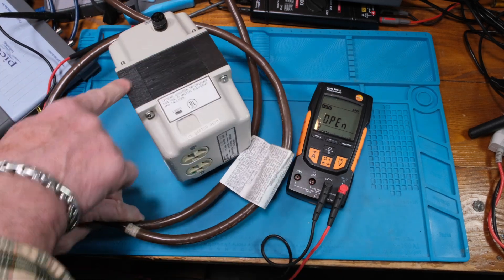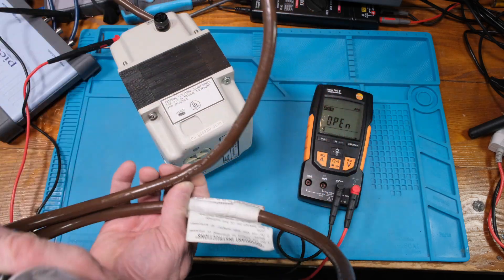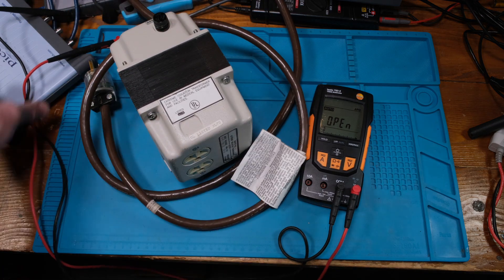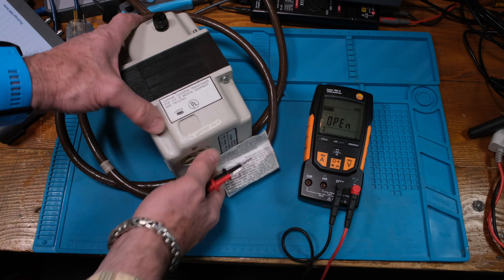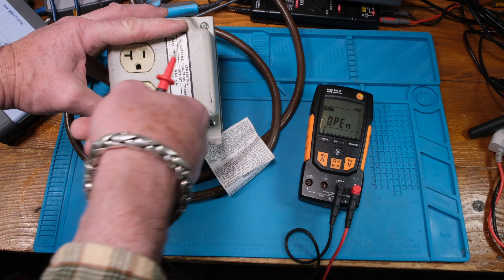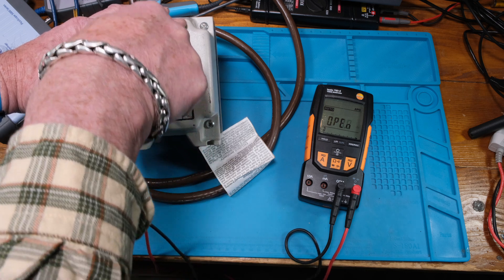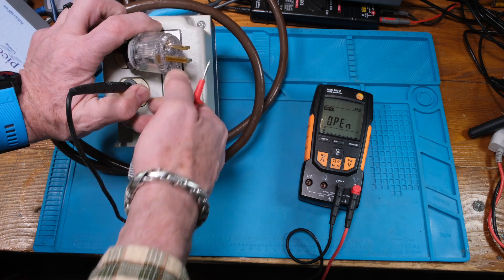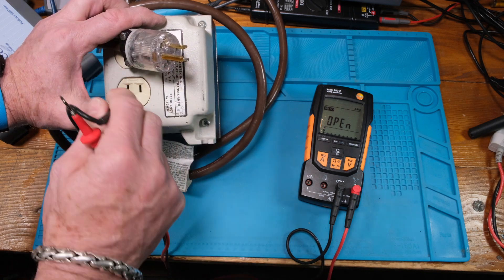You can see the iron slabs and a nice size cord. One thing about hospital-grade connectors is that the leakage current to ground is supposed to be limited so it doesn't cause problems with electronic or hospital equipment. Both receptacles are connected on the output side but isolated from the input side — except for the ground, because the metal chassis needs to be grounded for safety.